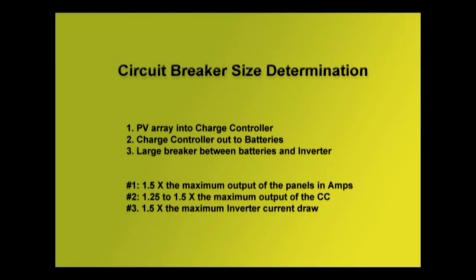And the number 3, the larger breaker between the batteries and the inverter. In other words, the battery bank's output going into that inverter. It's going to be a larger breaker. Number 1 needs to be 1.5 times the maximum output of the panels in amps, around 1.5. Those panels can actually put more power out instantaneously because of a little bit of a lensing effect. When the sun comes out from behind clouds, there'll be an increased power, so you do need a little bit of elbow room there. 1.5 is a good place to be around that level.